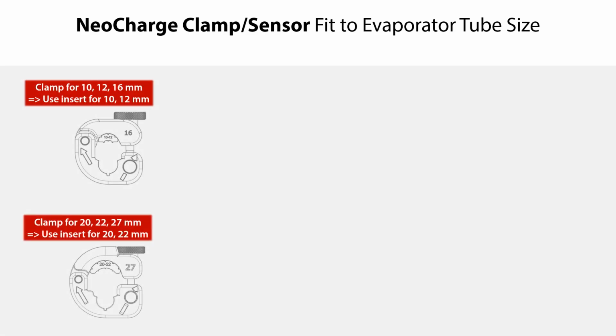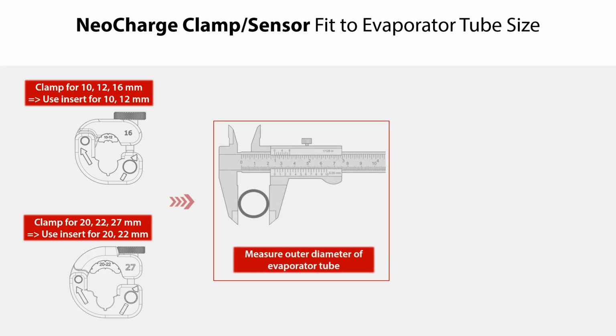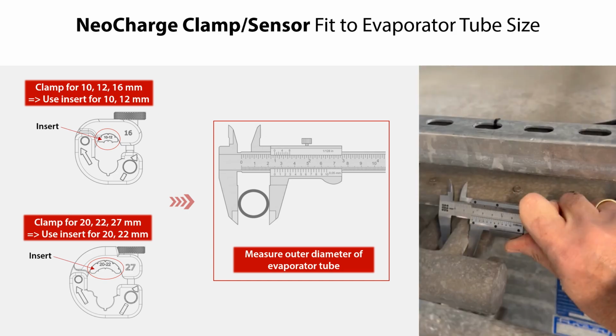As seen here, there are two sizes of sensor clamps depending on the outer diameter of evaporator tubes. Therefore, as mentioned earlier in this video, it is important to measure the evaporator tube diameter already before ordering the Neocharge to ensure that the correct code number is ordered. However, as also mentioned earlier and as seen here, there is a clamp insert included for both clamp sizes so that the clamp can be adjusted to the given outer diameter. Therefore, you need to measure the tube outer diameter as shown here to see if the clamp insert is needed.